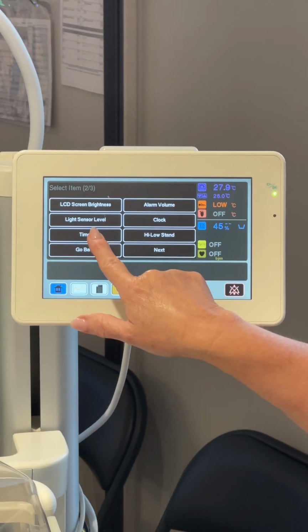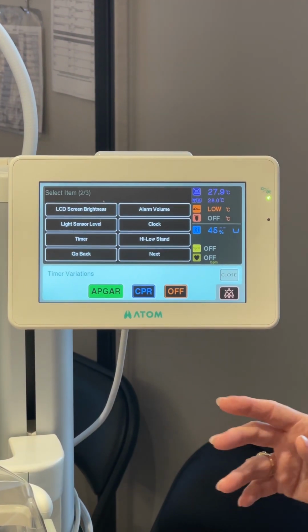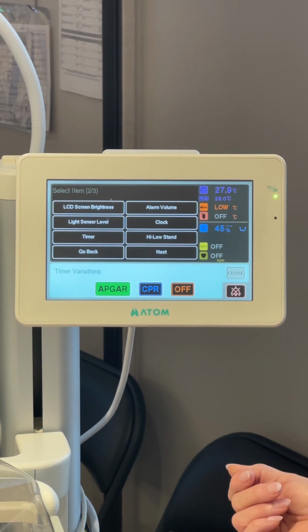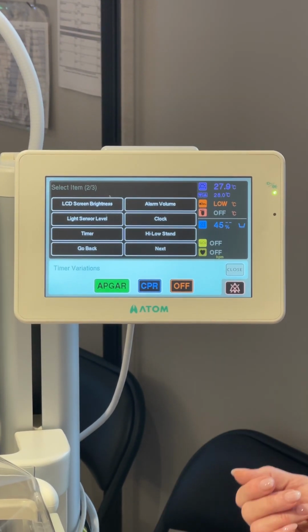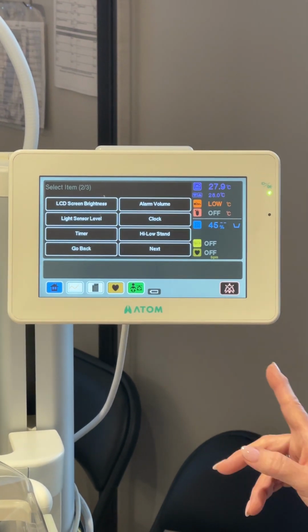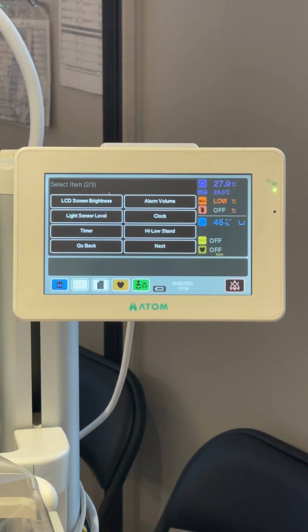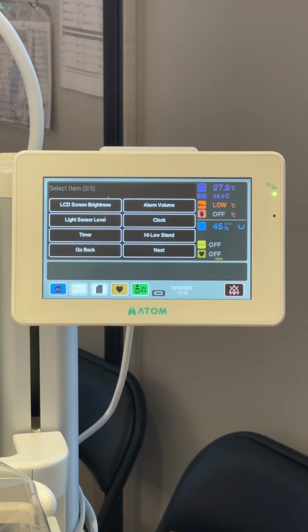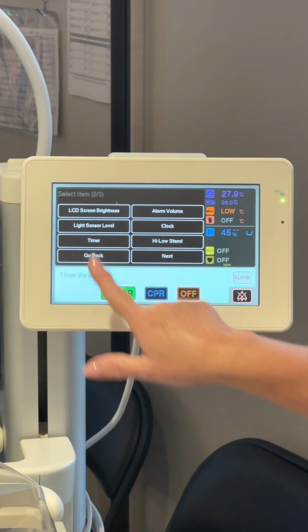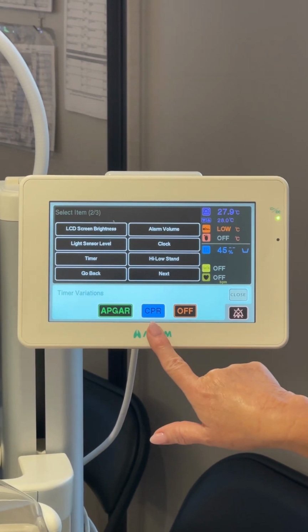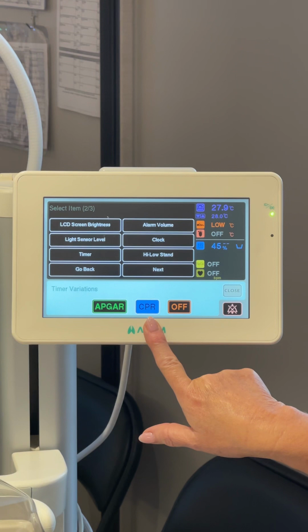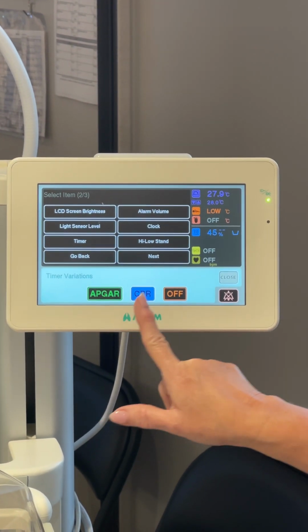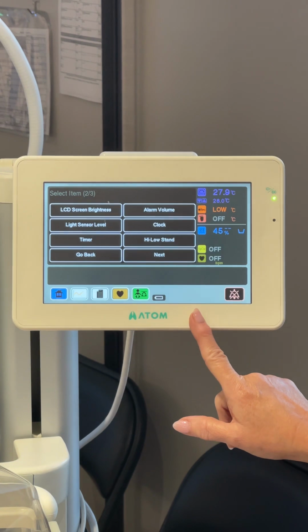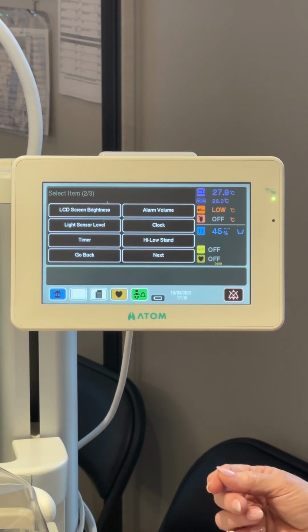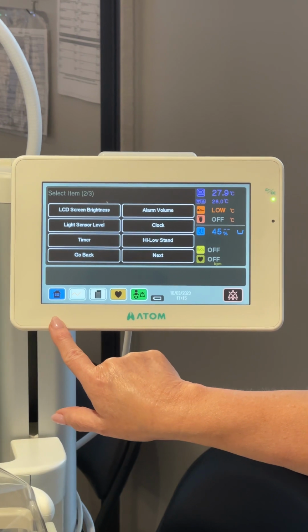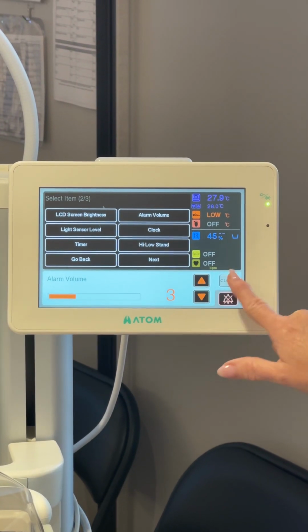But I like the APGAR timer on here for all times, because the APGAR timer does a full 60-minute count, gives you alerts at 1, 5, and 10. But I like it in NICU because you can use it for any time you need a timer at your finger's touch, such as your golden hour or timing a feed or whatnot. I like it. And the only difference between that and the CPR timer is that every 30 seconds, the CPR timer will give you a reminder to do your NRP heart rate assessment, as well as give you a 6-second visual count, so that you can count your heart rate, multiply it by 10, and call it out every 30 seconds. Alarm volume, very easy to change.